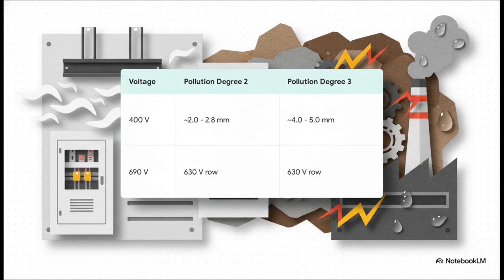Consider the jump from pollution degree 2 to degree 3 at 400 volts. The required surface creepage distance almost doubles, going from around 2 to 2.8 millimeters all the way up to 4 or 5 millimeters. Why? Because environmental factors like conductive dust, humidity, and condensation in an industrial workshop or motor control center significantly increase the risk of electrical tracking compared to, say, a pristine, clean electrical room.